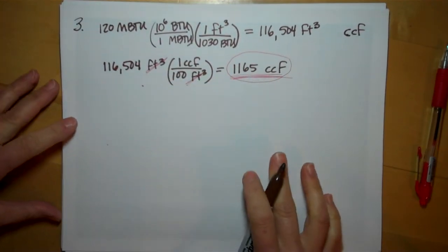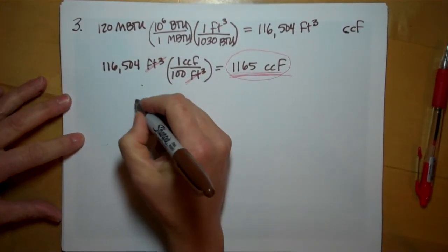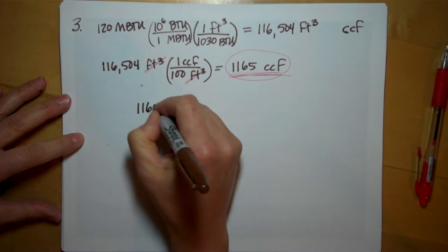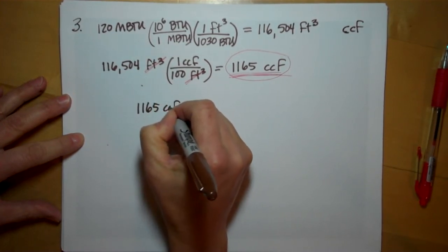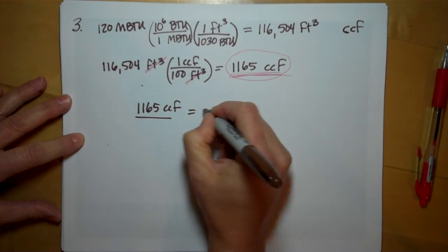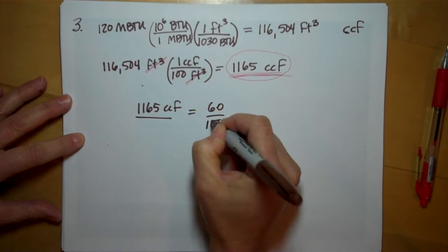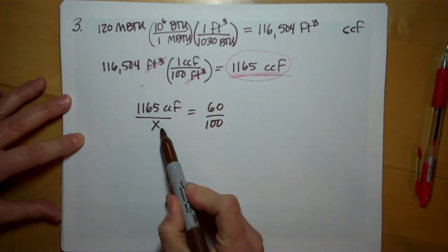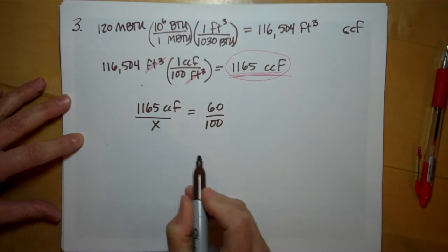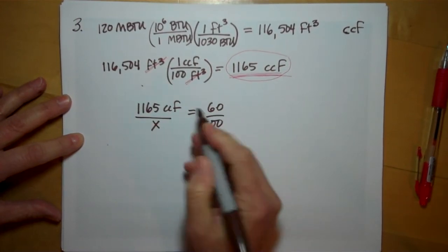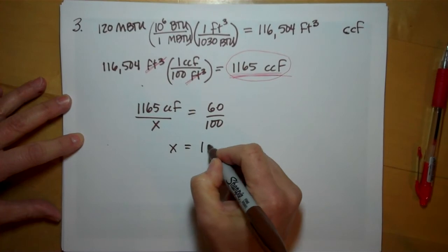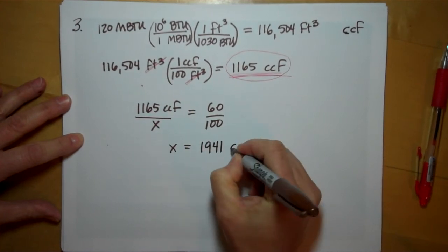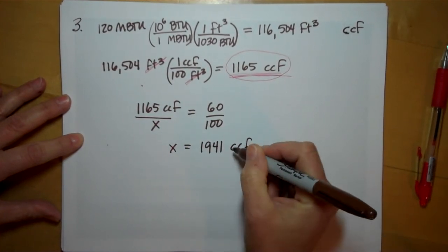So if we do a simple proportion with percents, if 1165 CCF is supposed to be the 60% efficient, what's going to be X? So just cross multiplying, X comes out to 1,941 CCF.